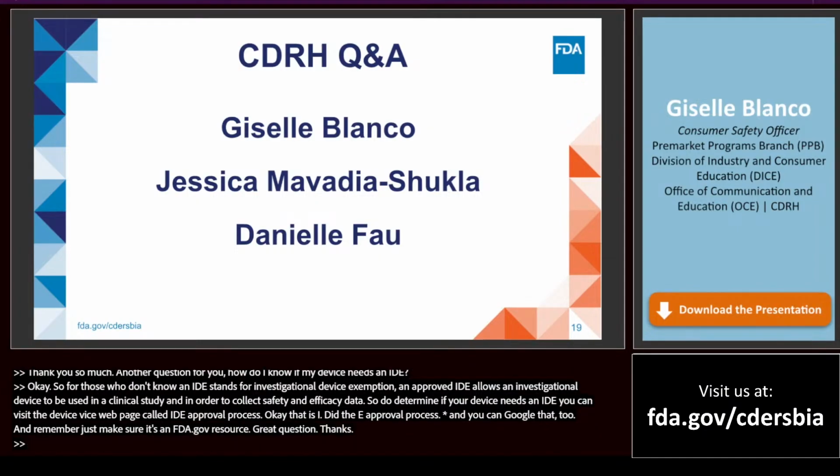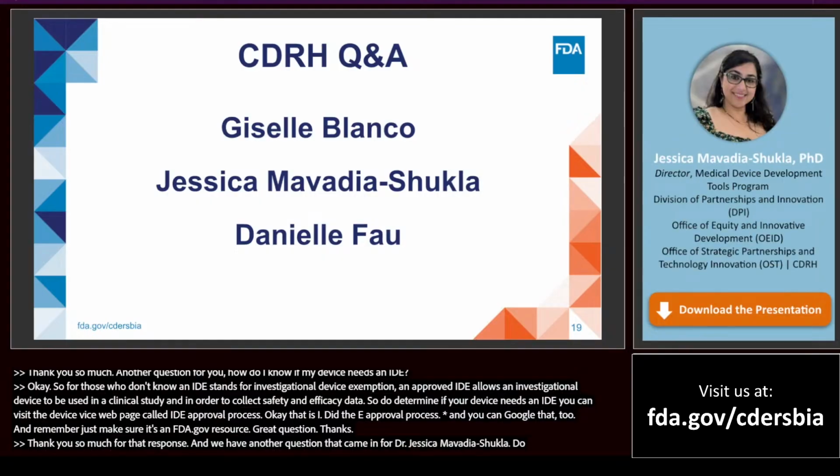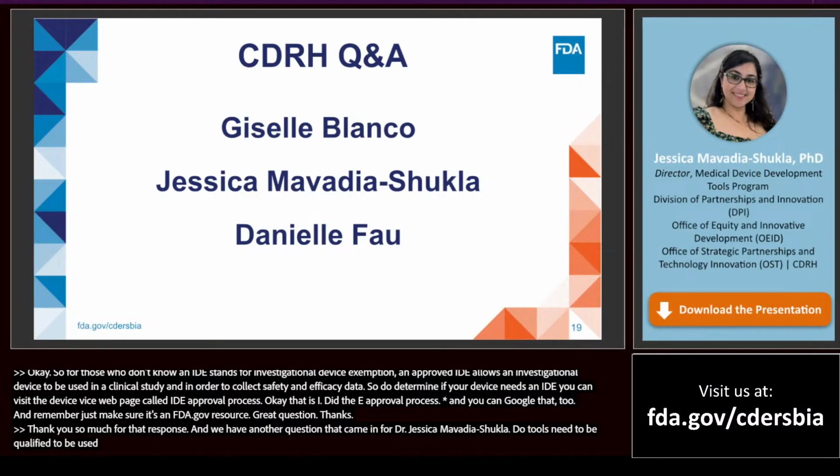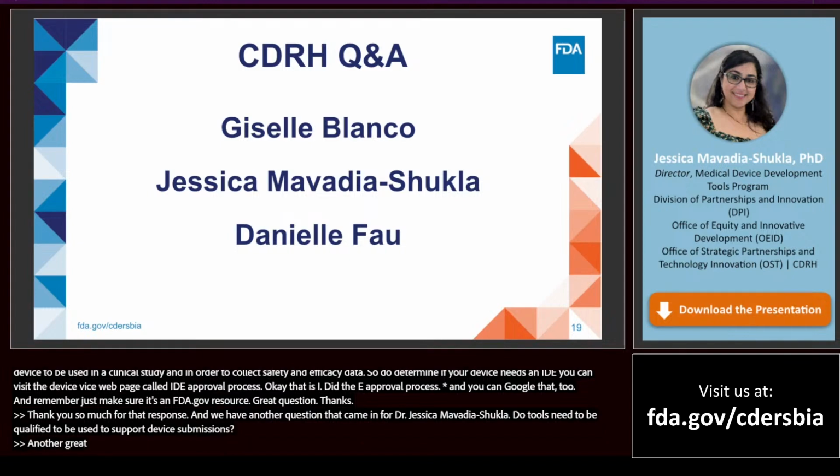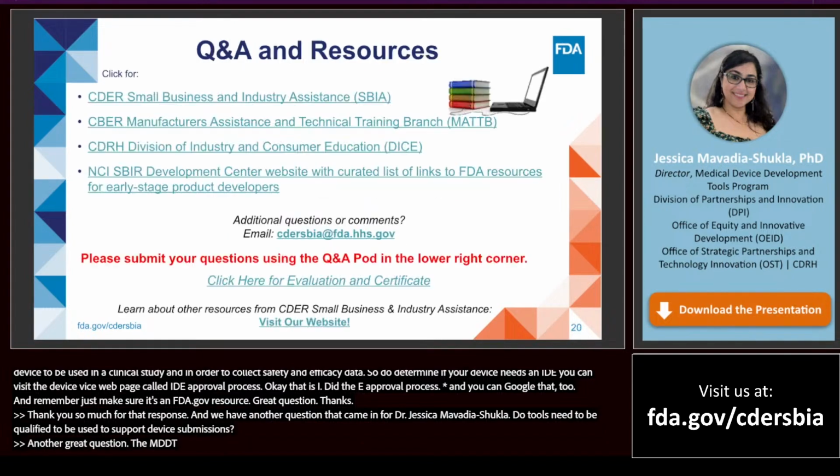Thank you so much for that response. And we have another question that came in for Dr. Jessica Mavadia-Shukla. Do tools need to be qualified to be used to support device submissions? Thanks, Nora. Another great question. So the MDDT program and qualification is voluntary.